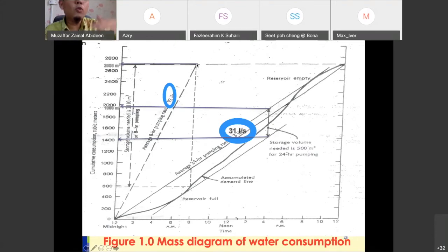So, how much water, what is the volume needed for that eight hours? How do we do that is by obtaining this value 2685 minus the volume at eight o'clock, which is 582 meter cube. You can obtain it from table. So the maximum value is 2685 and the amount of water at eight o'clock is 582 meter cube. So you have 2685 minus 582. So that is the equalizing demand when we start the pump for eight hours.